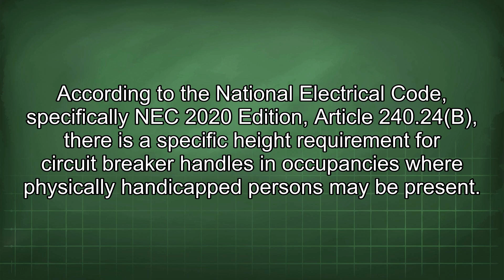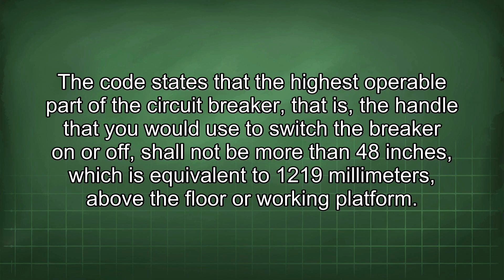According to the National Electrical Code, specifically the NEC 2020 edition, Article 240.24(B), there is a specific height requirement for circuit breaker handles in occupancies where physically handicapped persons may be present. The code states that the highest operable part of the circuit breaker, that is, the handle that you would use to switch the breaker on or off, shall not be more than 48 inches, which is equivalent to 1219 millimeters, above the floor or working platform.